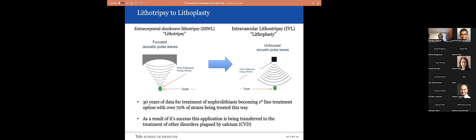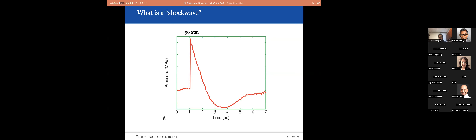treatment of calcified disease. So what is an actual shockwave? It's a dramatic increase or a jolt of sonic pressure waves that generate 50 atmospheres of pressure for an exceedingly short period of time and then dissipates the energy within a few microseconds. Non-compliant balloons will increase the pressure up to 26 or 30 atmospheres at most, and I think few people would even use it at that pressure unless they absolutely had to, and that pressure is transmitted somewhat slowly over time, whereas this is very quickly with a dramatically higher atmospheric pressure.